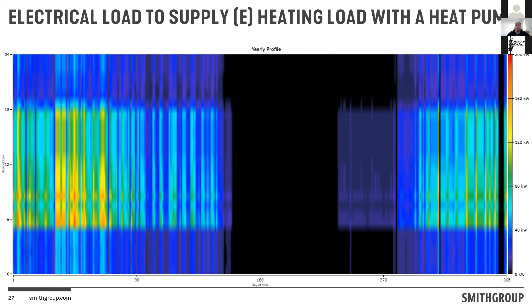What we strongly recommend is that when doing design considerations, you look at the duration that peak occurs. We highly encourage folks to include thermal energy storage as a means to shave that peak. You don't have to do batteries—if you compare pound for pound or dollar for dollar, thermal energy storage is still a sexy technology that is super dumb, but extremely easy to maintain. It's extremely benign environmentally, and it can drastically reduce the number of heat pumps I need to install if I can shave those peaks.